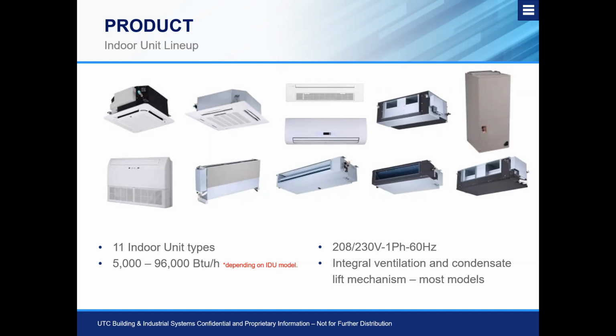The floor console unit does have an accessory condensate lift, but it does not come with the indoor unit from the factory. If we are specifying that we need a condensate lift, we need to make sure we do so on that model. Of course, outside air can be ducted into any one of the four. And then we have our ducted units. Our low static is going to have a built-in condensate lift. Our mid static is going to have a built-in condensate lift. Our high static is not going to have a built-in condensate lift. So it's important to know that on the high static unit, we're going to need an external pump. All three of those have outside air for ventilation mixed in at the return, but that air again needs to be pre-treated.